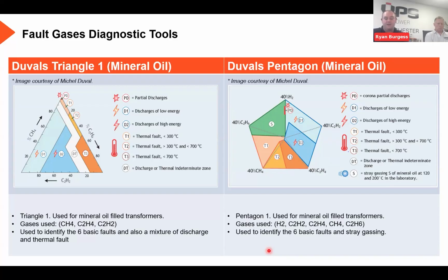Then you have methane, which is a low thermal fault indicator, and that's typically produced due to things such as basic overheating. So that overheating can be due to poor circulation, or something even as basic as a load of debris around the transformer on the outside, especially here in the UK this time of year, all the leaves blocking the radiator, so the heat isn't effectively distributed from the external of the transformer like it should be.